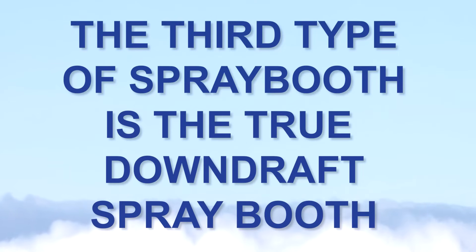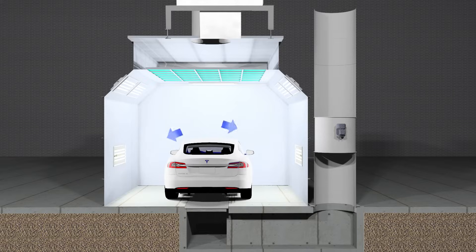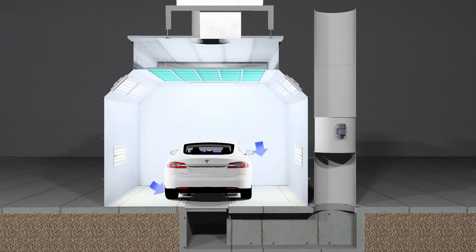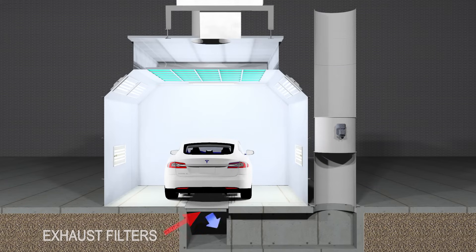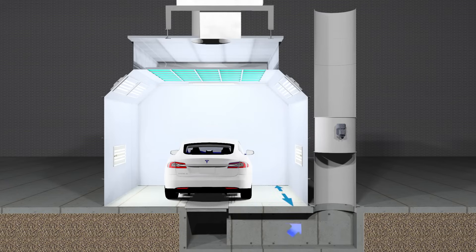The third and the best type of spray booth for any spray painting application is the true downdraft spray booth. Similar to the modified downdraft spray booth, it has its intake or incoming air coming directly above the product being painted. But the difference in the true downdraft airflow is the exhaust filters are directly below the product being painted. Since in almost every situation the height of a spray booth is going to be shorter than its length, that air coming from the ceiling and going directly to the floor under the product being sprayed has a shorter distance to travel.